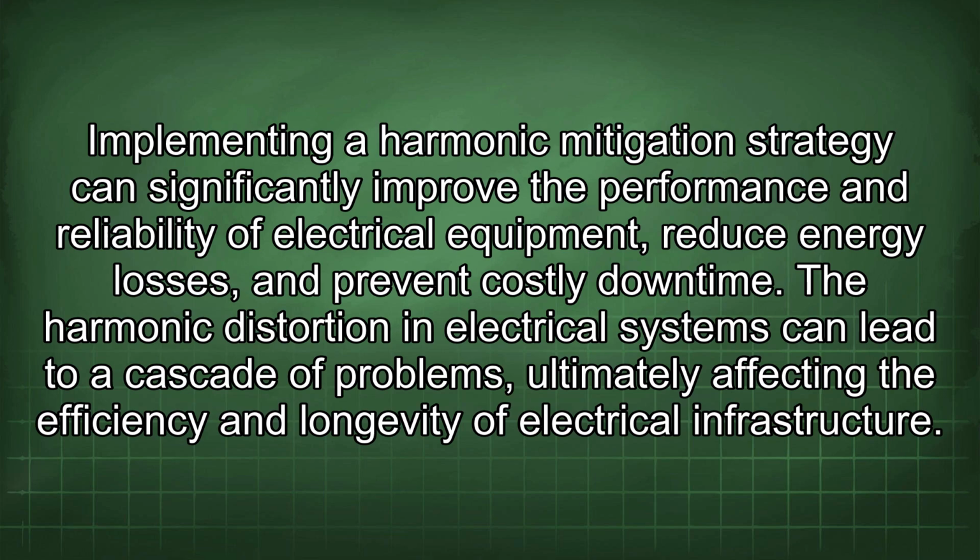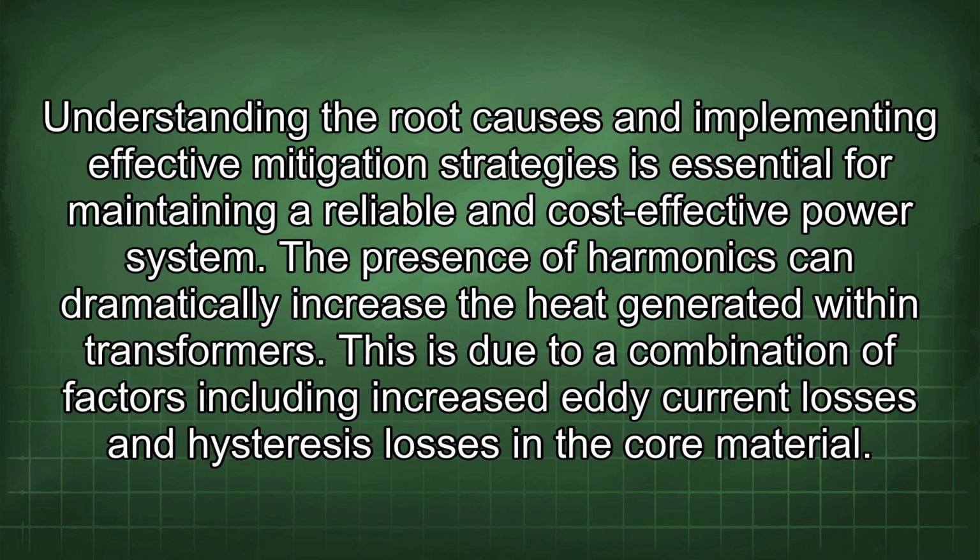The harmonic distortion in electrical systems can lead to a cascade of problems, ultimately affecting the efficiency and longevity of electrical infrastructure. Understanding the root causes and implementing effective mitigation strategies is essential for maintaining a reliable and cost-effective power system. The presence of harmonics can dramatically increase the heat generated within transformers.